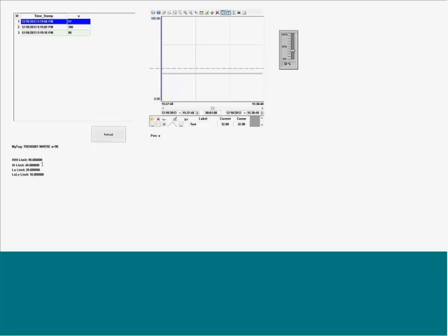What you cannot have is assign two high limits for the same tag. You can have a high and a high high. You can have a low and a low low. You cannot have two highs or two lows. But using high, low, deviation plus and minus, and rate of variation, you can have up to 7 alarms assigned to each tag.